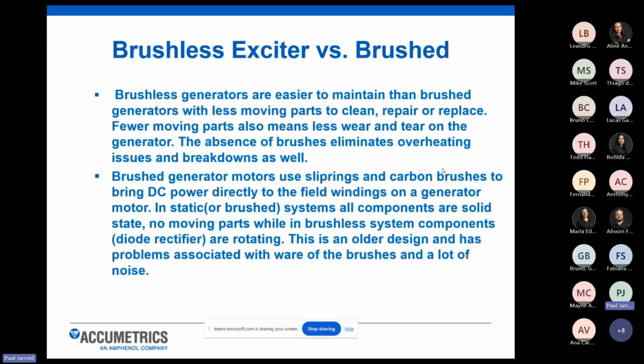Okay, so we're going to talk next about brushless exciters versus brushed exciters. Generator rotors require excitation voltage to power the rotor windings. Essentially, you can think of it as the power source or power supply for the generator rotor field windings. Most generation facilities have two types of excitation systems: brushless exciters and brushed or static exciters. Our focus at Accumetrics is to support the brushless generator market. A lot of the new machines being built from many of the manufacturers out there are in fact brushless. Brushed tends to be an older technology. A lot of the manufacturers are going away from brushed and moving into the brushless world.